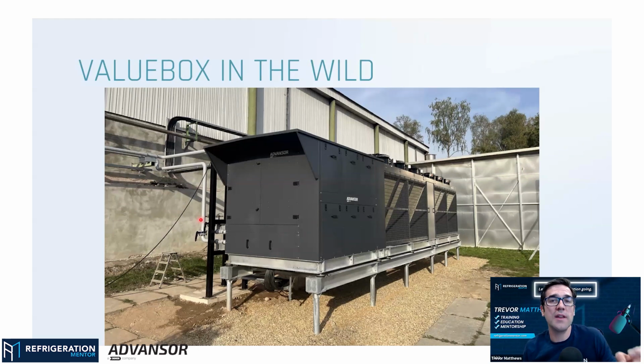So for these high pressure valves, like everyone's like, these ejector valves, these single ejectors, oh, I don't know how it works. It is just an electronic valve. There's a motor on it. It's going to open and close the orifice to make it bigger, just like Erik said, to shoot out. What is that going to be controlled by? So in your heat pump, what is controlling that to open and close to say, okay, we need more lift, we need less lift? So if someone's going to go in and look at your controls, if it's a Danfoss or Carel or whoever it is, doesn't matter, what is controlling that ejector for your system to make it most optimal, to make sure that it's always running at the best COP?